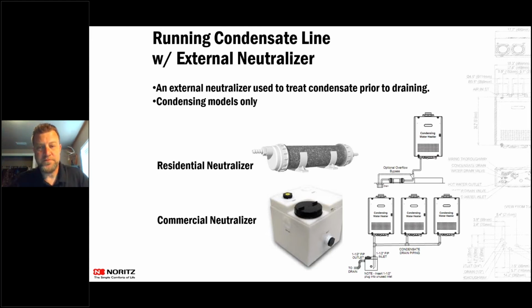Okay, thank you. I was going to say, if you don't neutralize that and you're on a cast iron drain, it will eat your drain out. Yes. So it's best to neutralize unless you're in plastic drain lines. Some of these older houses, it eats those P-traps right out, so be careful with that. If they've got cast iron or galvanized, older drainage and it's not plastic, I would highly recommend neutralizing that condensate so you don't eat away their drainage system. Okay, thank you.